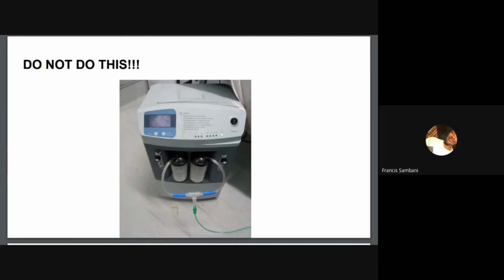What you're trying to avoid here is that if you set the flow meter on the oxygen concentrator at 3, and you're also trying to draw 3 liters on the flow splitter, you don't necessarily get the 3 liters that you want. As you try to adjust one flow knob, the other flows also readjust. So you're just chasing an endless thing. That's why when using flow splitters, you should always give it that +1 buffer, so that you work well with it.